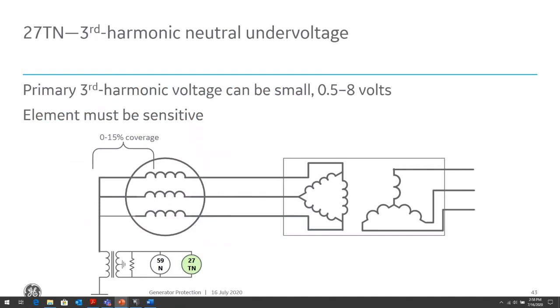However, the combination of the 59N and the 27TN allows us to get good coverage. So the 27TN can protect the last 15% of the winding, and the 59N will protect 90% of the winding. So they have overlapping coverage between the two. So normally we'll see a combination of these two types of protection.